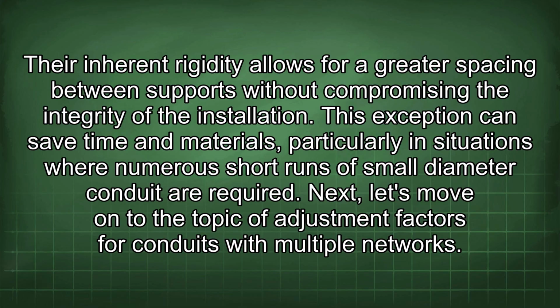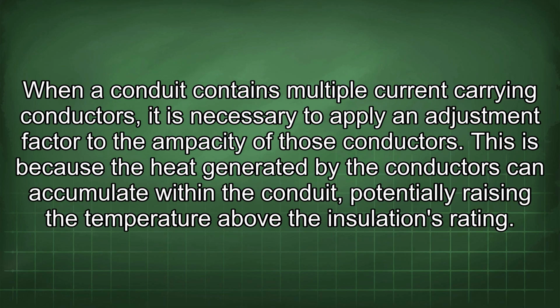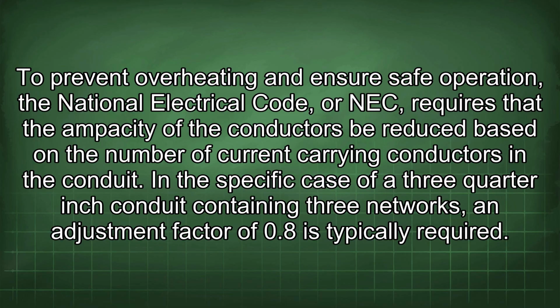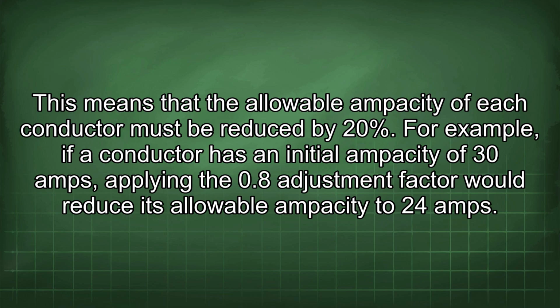Next, let's move on to the topic of adjustment factors for conduits with multiple conductors. When a conduit contains multiple current-carrying conductors, it is necessary to apply an adjustment factor to the ampacity of those conductors. This is because the heat generated by the conductors can accumulate within the conduit, potentially raising the temperature above the insulation's rating. To prevent overheating and ensure safe operation, the National Electrical Code, or NEC, requires that the ampacity of the conductors be reduced based on the number of current-carrying conductors in the conduit. In the specific case of a 3/4 inch conduit containing 3 conductors, an adjustment factor of 0.8 is typically required. This means that the allowable ampacity of each conductor must be reduced by 20%. For example, if a conductor has an initial ampacity of 30 amps, applying the 0.8 adjustment factor would reduce its allowable ampacity to 24 amps.